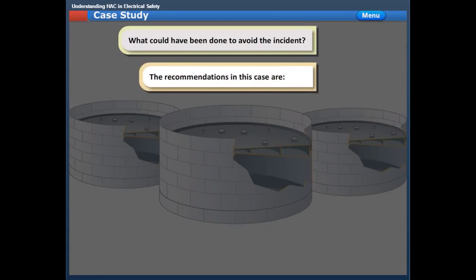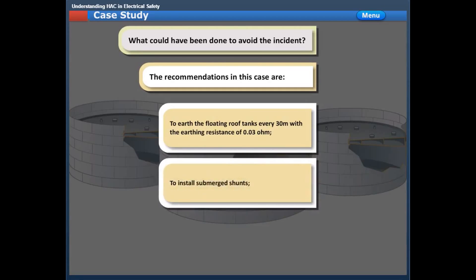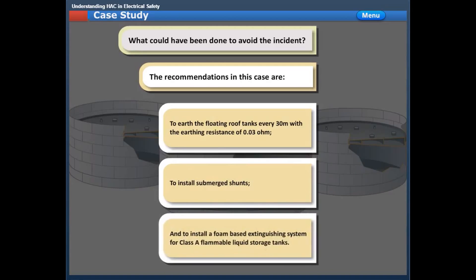The recommendations in this case are: to earth the floating roof tanks every 30 meters with an earthing resistance of 0.03 ohm; to install submerged shunts; and to install a foam-based extinguishing system for Class A flammable liquid storage tanks.